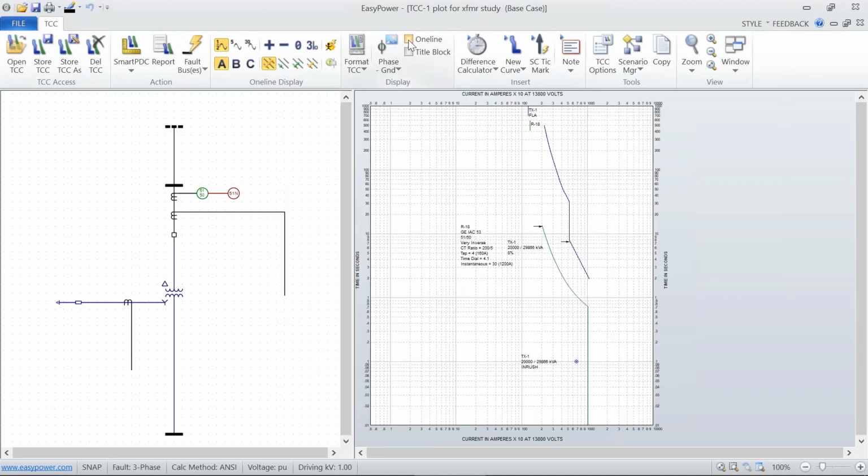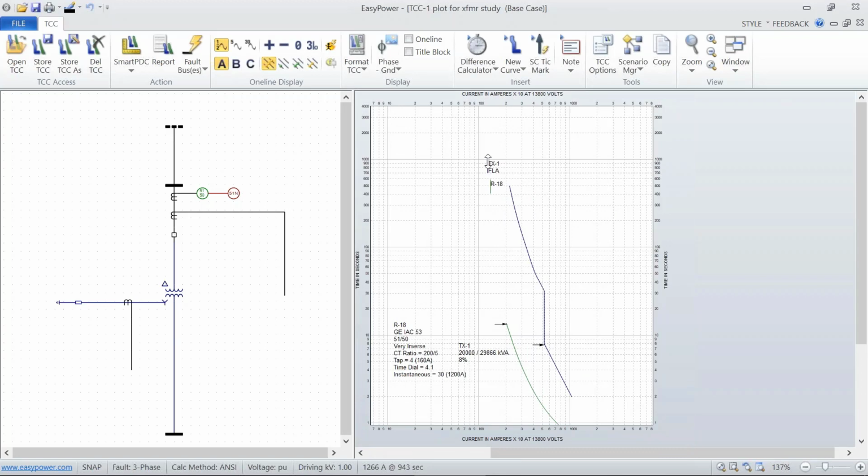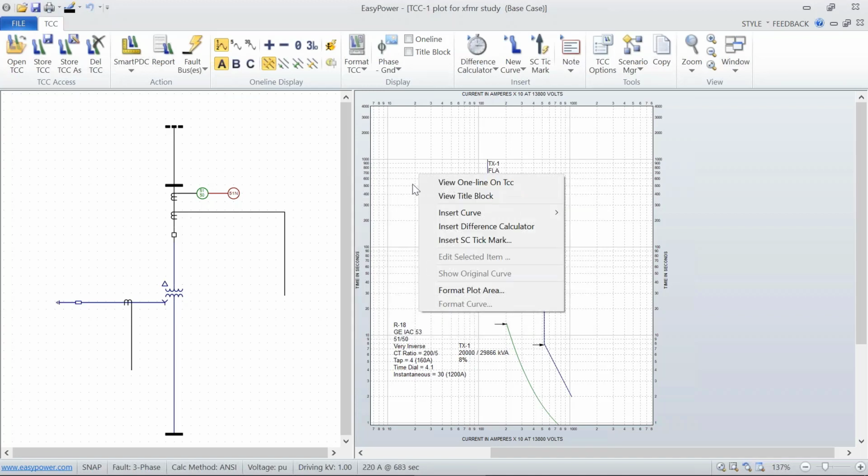And what we see now is our transformer max full load current is going to be shown down here in my cursor coordinates. And if I center it right there, it shows 1237. It's like, wait a minute, Jim, I thought you said it was 150 amps. Well, it is, but we're looking at the 13.8kV side.